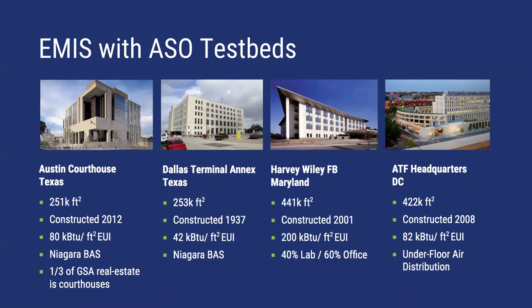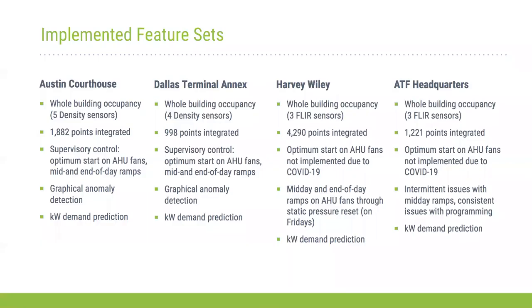Each building had different features implemented, as well as different BASs and different amounts of points integrated. These features depended on how the buildings were being evaluated: some were whole building energy savings, some were fan energy savings, and all 4 included peak demand prediction, a feature within the installed software. There were also 2 different types of occupancy counting sensors involved: 2 buildings had density sensors, and 2 buildings had forward-looking infrared radar sensors, or FLIR sensors.